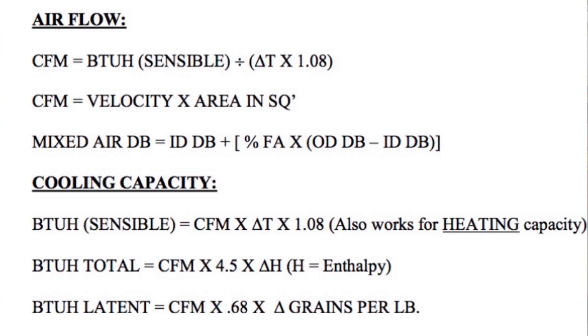Let's do a little mock example to go over how easy it is to get these calculations correct. Let's use a gas furnace because all of our cooling is going to involve some latent, so it will go to the total BTU equation — not the sensible. But for BTU sensible: let's say we have a gas furnace pushing out 1000 CFM, the delta T is 35, so we multiply 1000 by 35 then by 1.08.